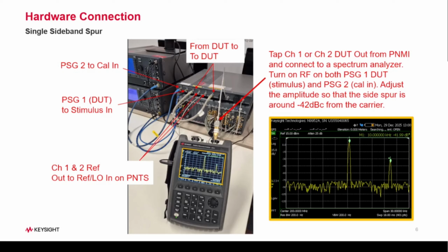So when we're running the calibration, first, just turn on the stimulus and turn off the signal of the single sideband cal port. And when you're asked to apply modulation, you would turn the RF power on the PSG2. All right, so let's now look into the phase noise test system.